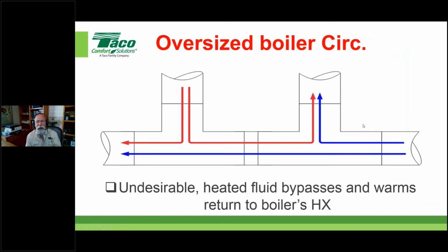Here's what we don't want to happen, right? Here's the thumbs down. So you can see this. It kind of shows you that if I oversize the boiler circulator, I have more flow going back across here and now blending that cooler water with the heated water, and now I'm reducing the overall boiler efficiency and the overall system efficiency. So that's undesirable.